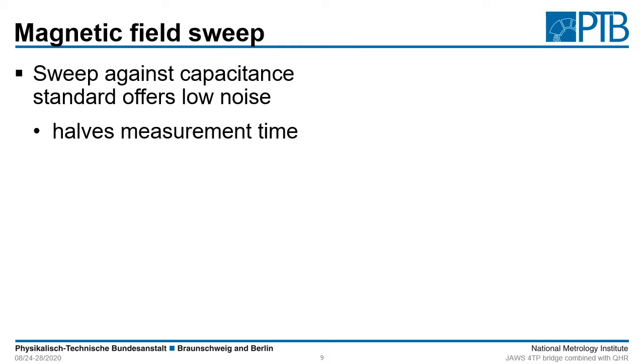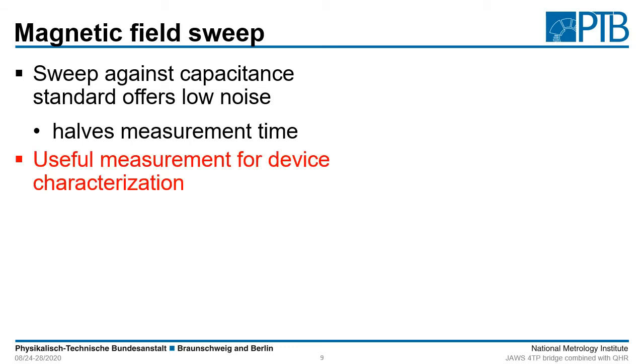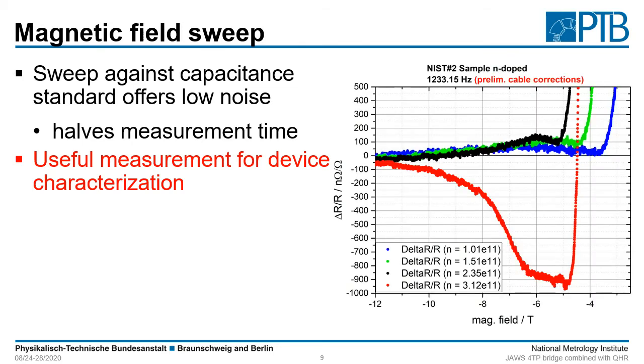One very important measurement for AC quantum hall devices is the sweep of the magnetic field. We performed these measurements, but against the regular procedure we did not measure against a room temperature resistor or a thermostat resistor but against a 10 nF capacitor. This has the great advantage of low noise and halves our measurement time, and it is a useful measurement to characterize devices. In this plot I show the relative deviation from the quantum hall DC value over the magnetic field for four different carrier density settings of the NIST sample.